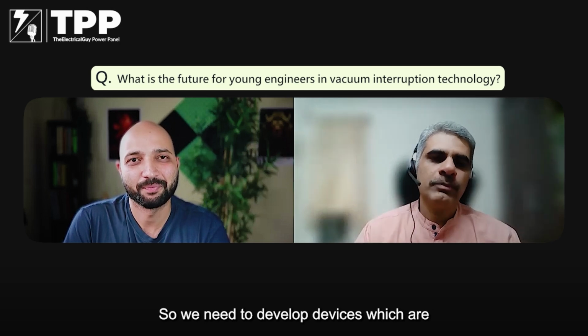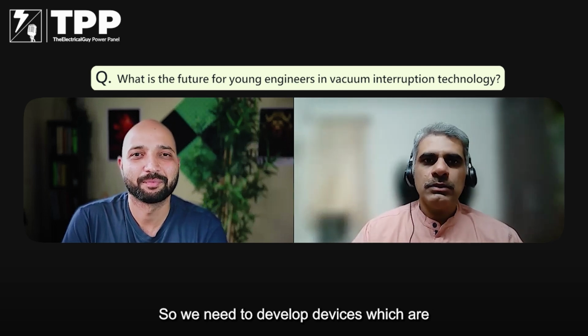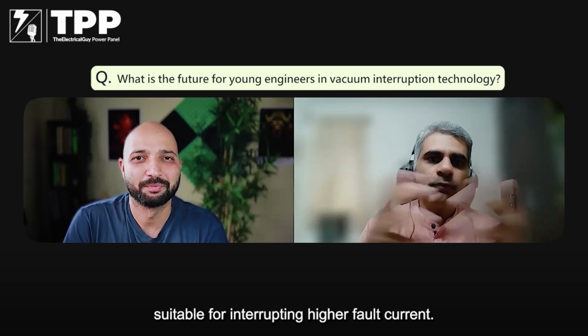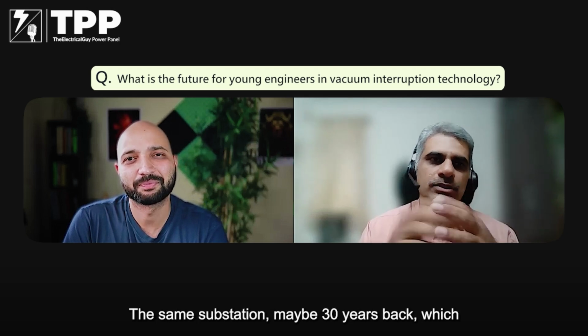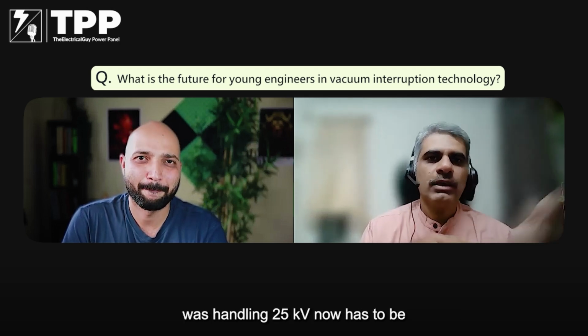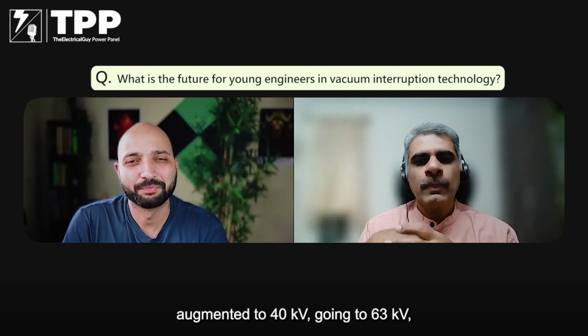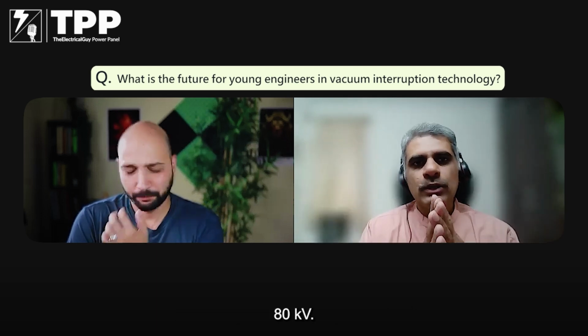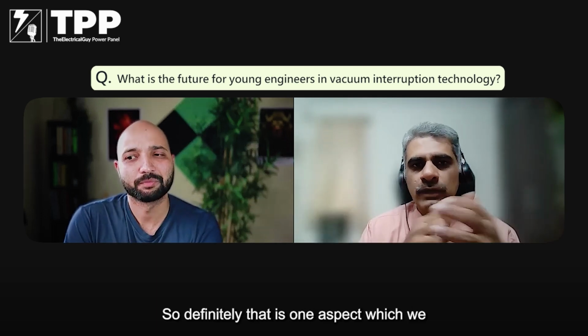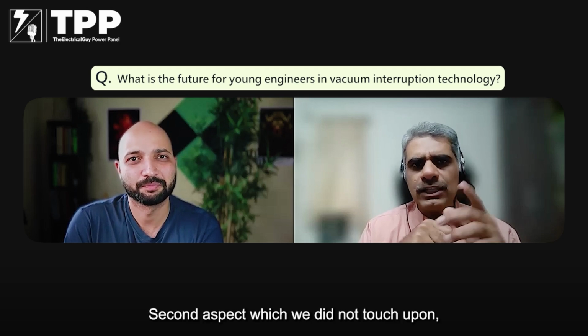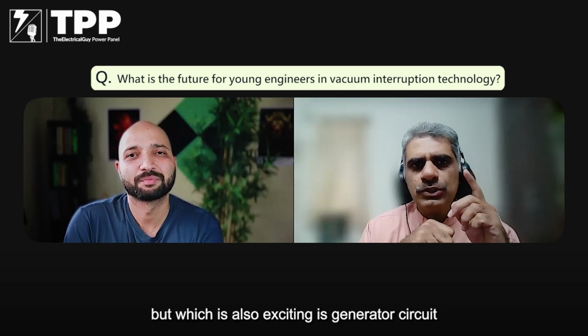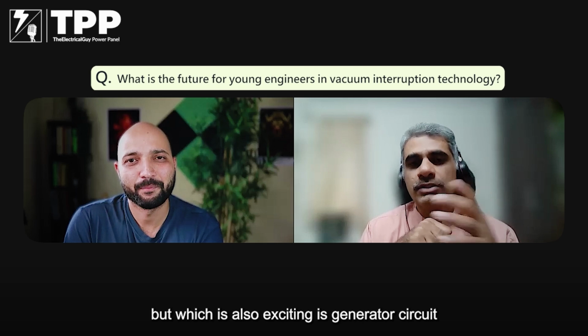So we need to develop devices which are suitable for interrupting higher fault currents. The same substation maybe 30 years back, which was handling 25K, now has to be augmented to 40K, going to 63K, 80K. So definitely that is one aspect which we need to look at. Second aspect which we did not touch upon, but which is also exciting, is generator circuit breakers.